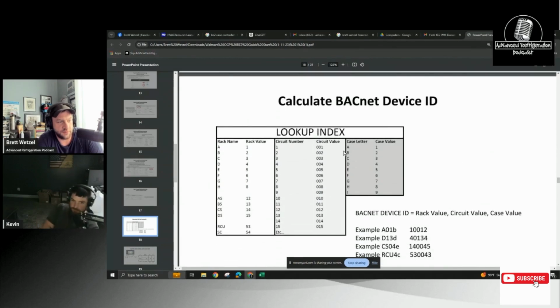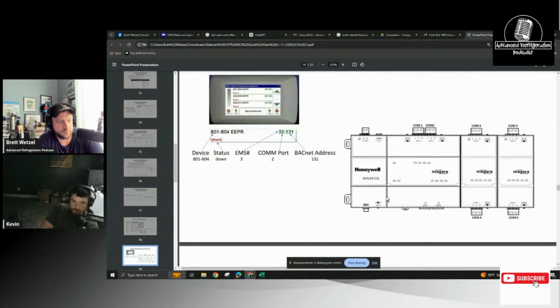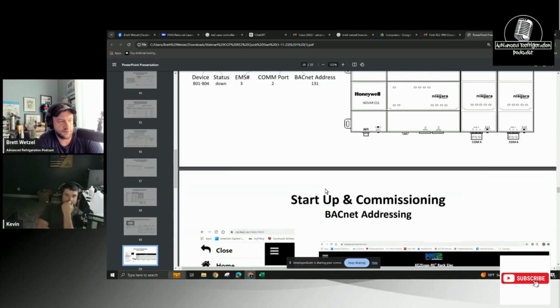So if you look down, see how that's B01? It shouldn't say B, this is the EPR. But if it was correct, it would say CS01A. That would be equal to 140011, which would be your BACnet address. The way it's spelled out is your instance ID.